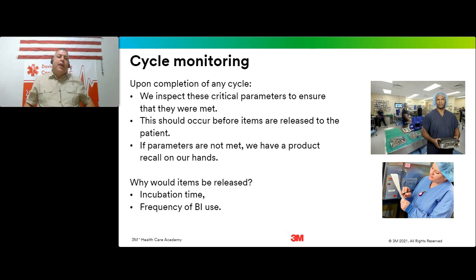Cycle monitoring. Okay, so hopefully we put all of our packaging together correctly, we load it into the sterilizer correctly, and all of our parameters are met, right? So once that cycle is complete, we want to inspect all of our parameters, run and incubate any tests that need to be incubated, and make sure that everything is good. If any of these parameters were not met, we could have a product recall on our hands.